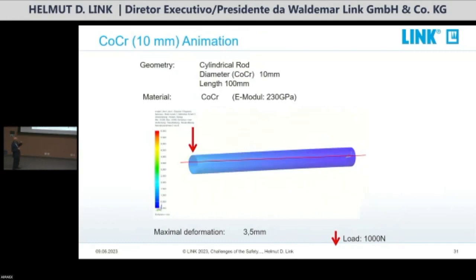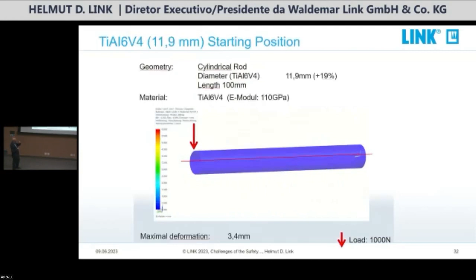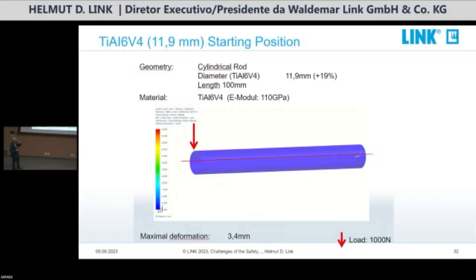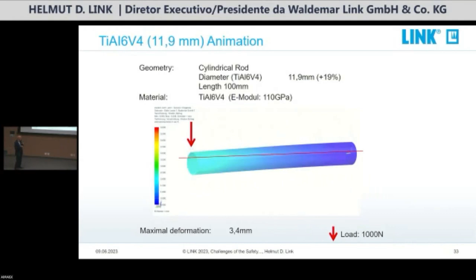But now, we increase the size of the titanium rod by only 19%. Still 110 gigapascal, still 1000 Newton, and the deformation is the same as the cobalt chromium rod. So in other words, if the size is right, you can also use titanium for cemented stems. That is something many surgeons, when we do it as custom made, for instance, and we provide titanium stems for cementing, tell us, no, titanium cannot be cemented. Wrong. If the size is good, you can cement it, but the size has to fit the necessity to protect the cement. So let's remember, the flexural stiffness of a system is defined mechanically as the product of Young's modulus and the geometrical moment.